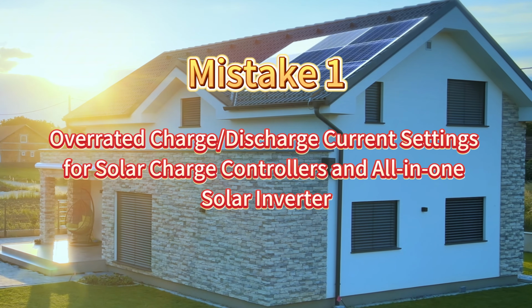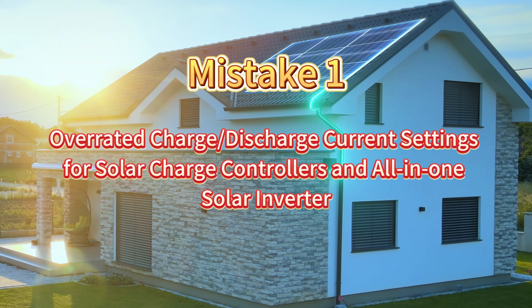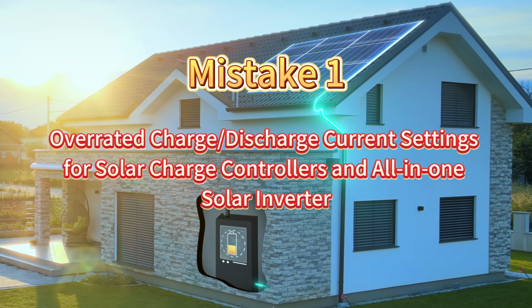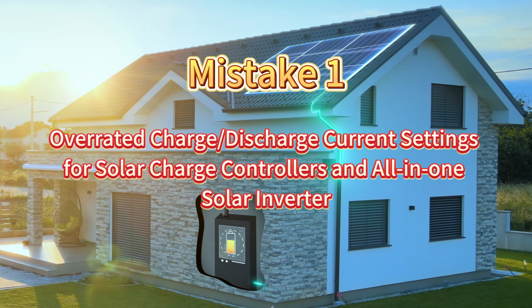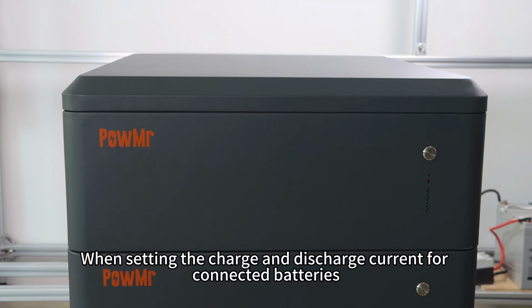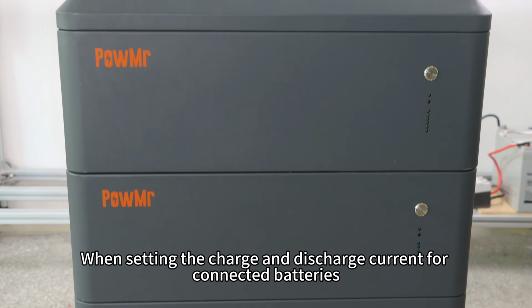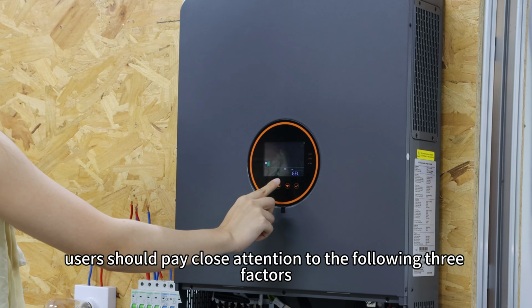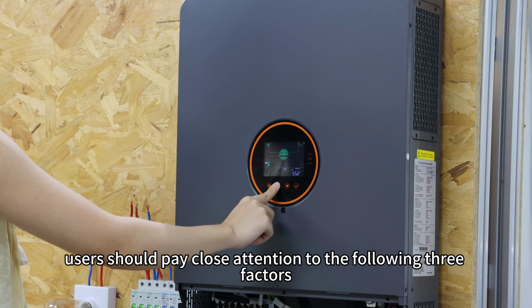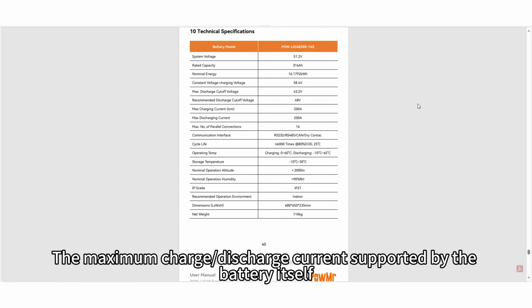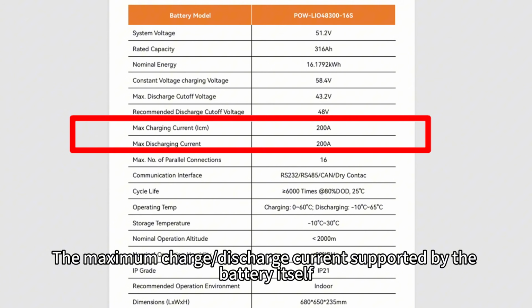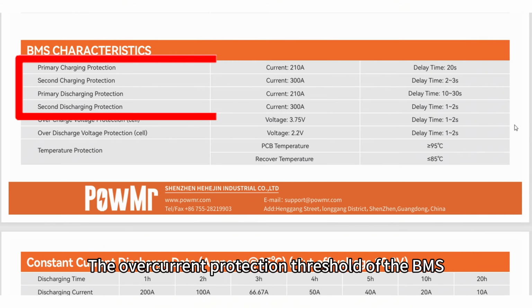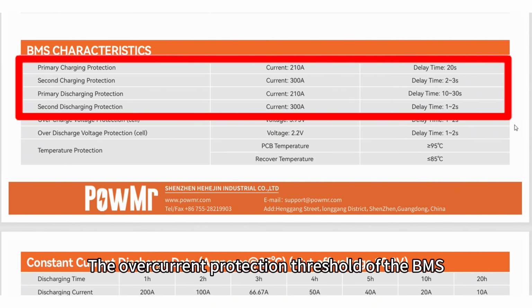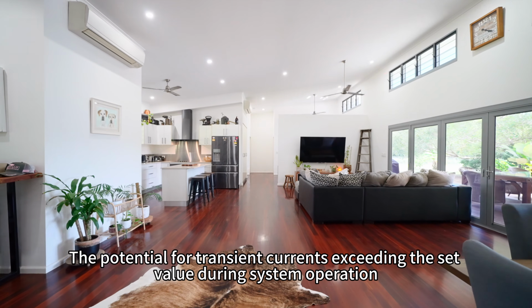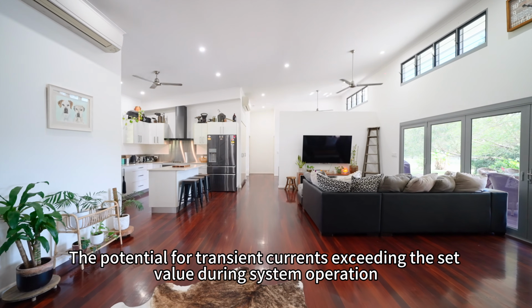Mistake 1. Overrated charge or discharge current settings for solar charge controllers and all-in-one inverters. When setting the charge and discharge current for connected batteries, users should pay close attention to the following three factors: the maximum charge or discharge current supported by the battery itself, the overcurrent protection threshold of the BMS, and the potential for transient current exceeding the set value during system operation.